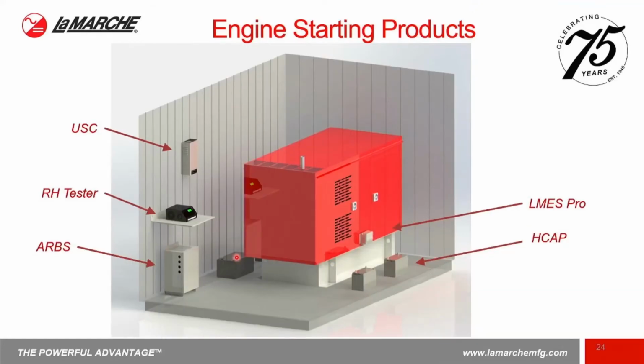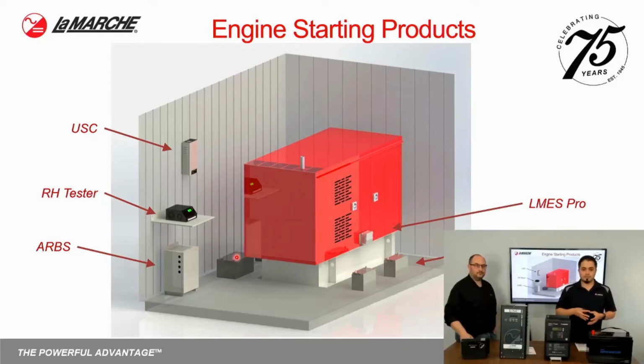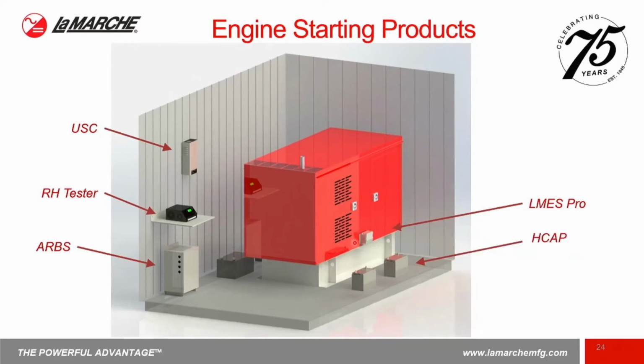Moving to the actual engine starting products themselves, here you have a nice graphic showing different typical locations. Obviously this is not the only situation they would look at. You can move them or use different orientations depending on the generator setup. Here you can see the LMES Pro is situated directly on the generator itself, where you can have it mounted on the wall, across the wall, or in a different area depending on your layout. Obviously smaller sites will have many more restrictions, and bigger setups will have much more available as far as adding redundant battery selectors, more batteries, or different setups.